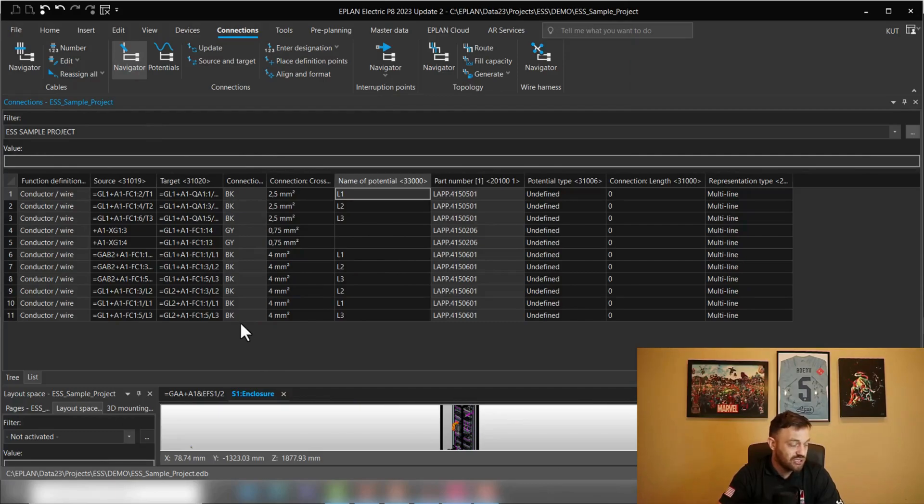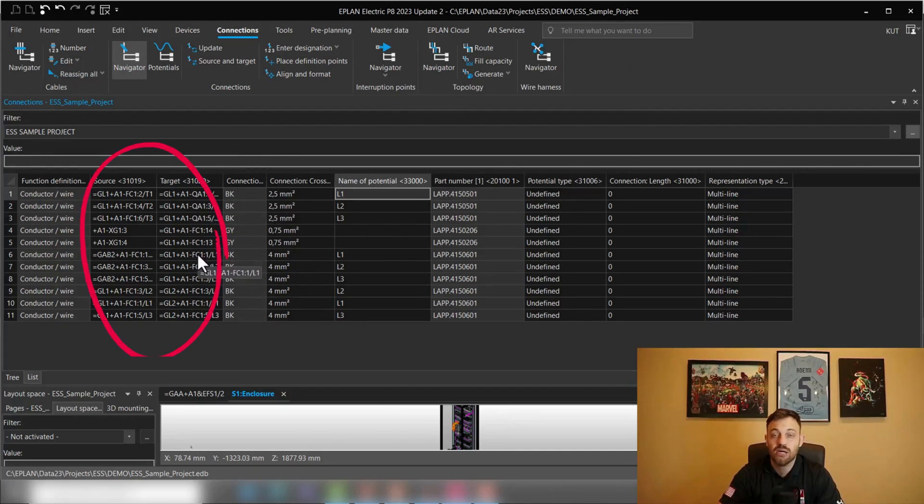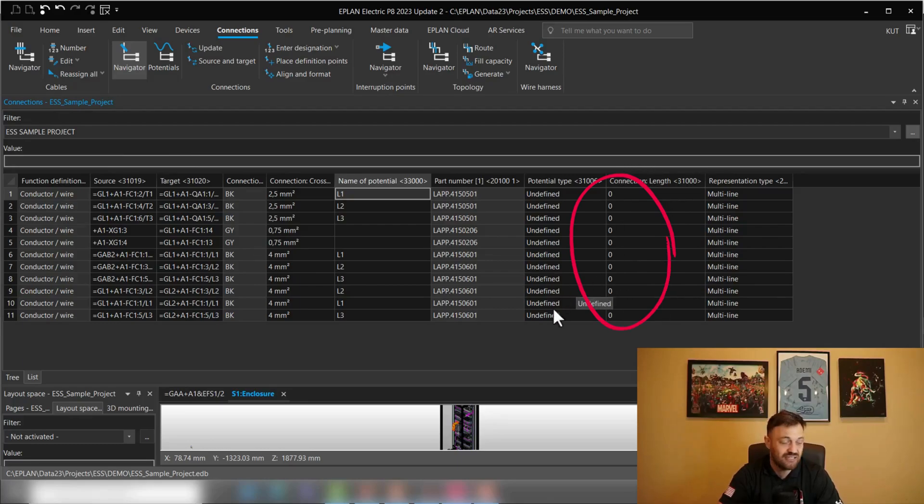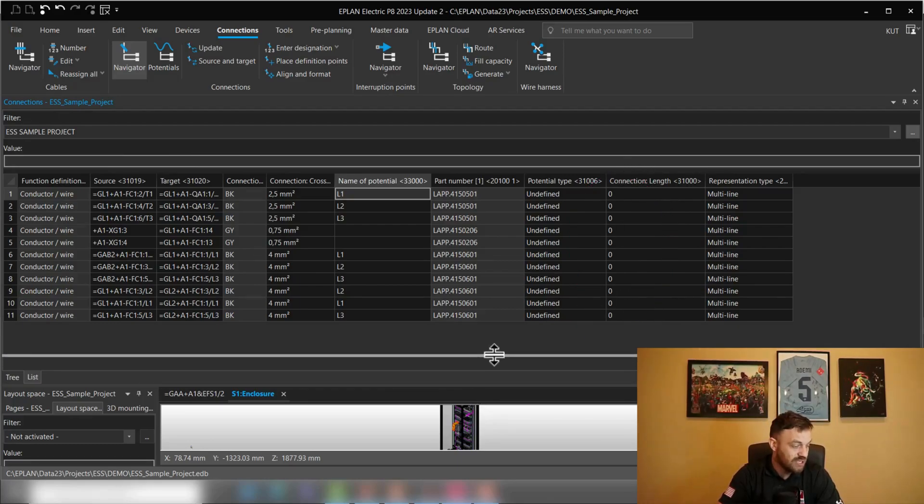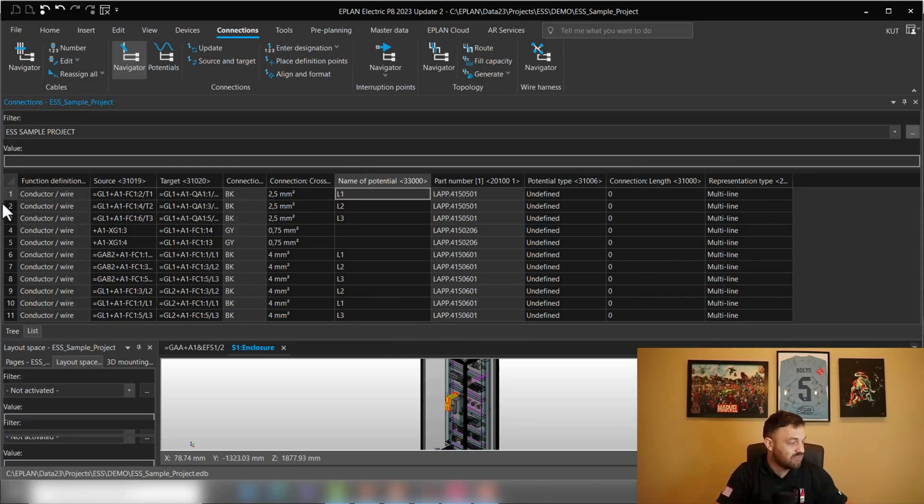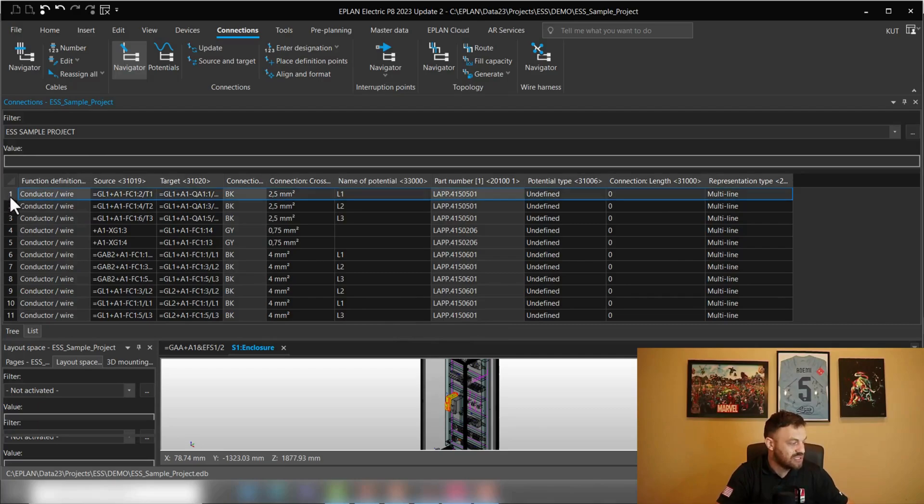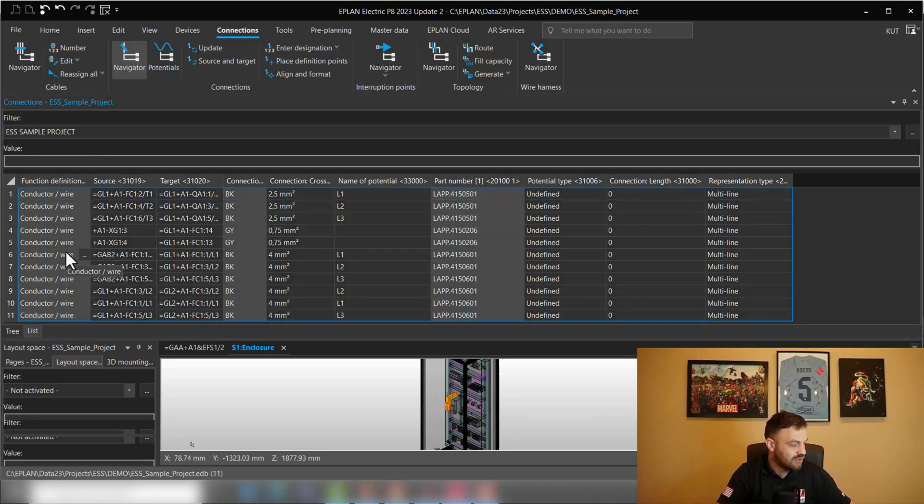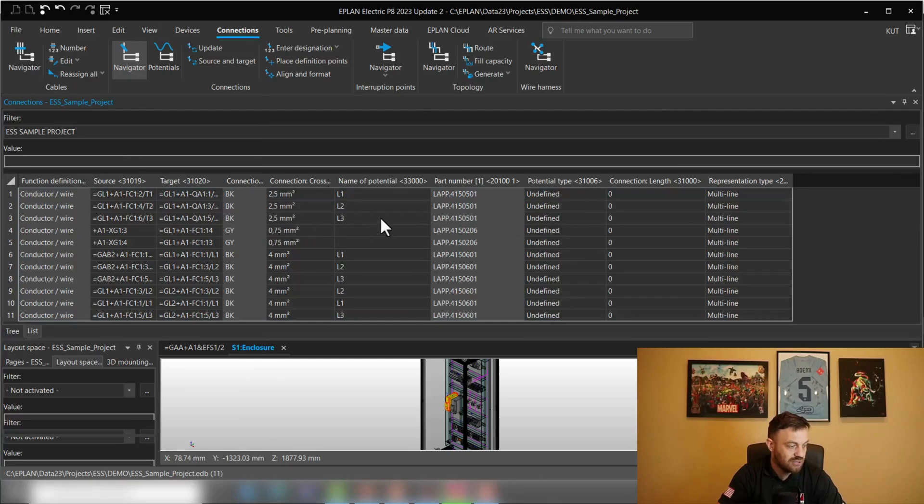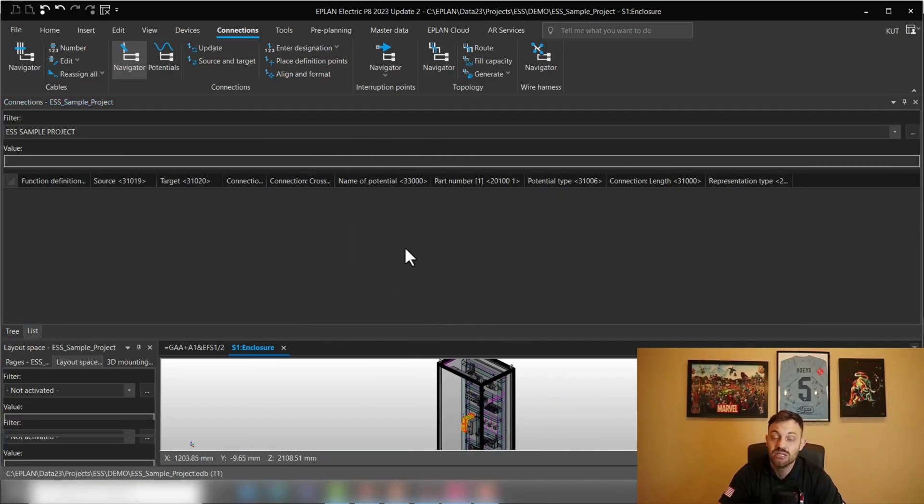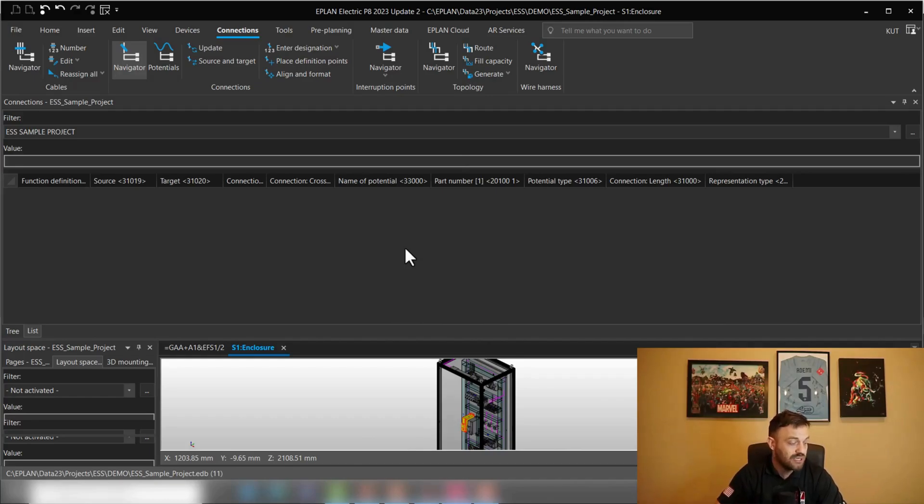So, the filter is essentially telling me that these 11 connections here need to be routed or are expected to be routed in ProPanel, but don't have a length yet. So, that means utilizing this filter, if I'm relatively new to the software, I'll probably just select these 11 wires. So, I'm going to control A, press right mouse click, and use the route functionality. Now, ePlan wired the wires, so they are already wired in ProPanel, and therefore, this list is empty.